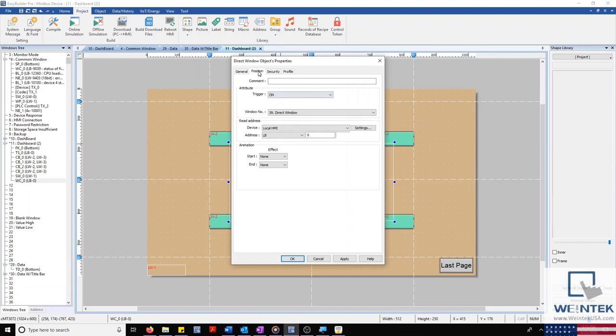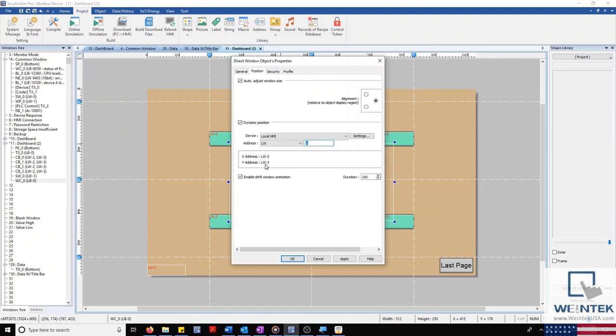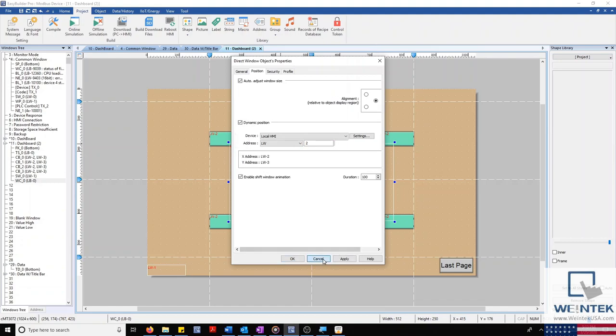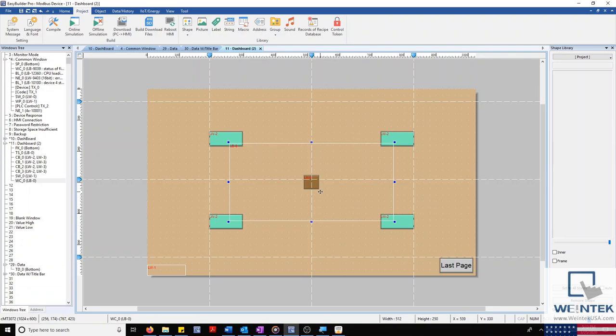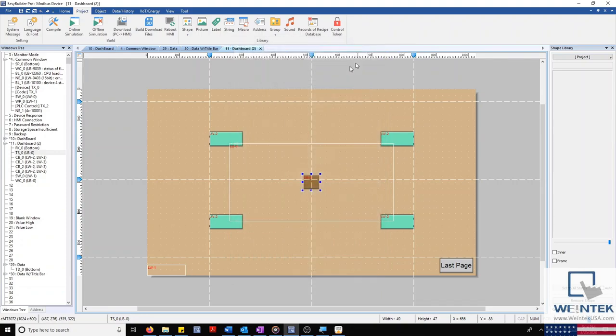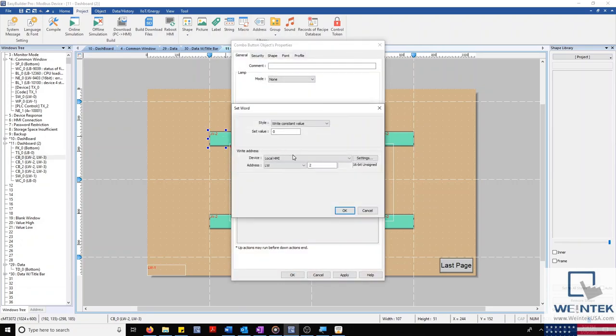Moving over to our Position tab, you'll notice a new feature found with EasyBuilder Pro version 6.04, called Dynamic Position. The Dynamic Position allows our window to change locations on screen to a user-specified location. To demonstrate this, I have a toggle switch located in the center of our screen, as well as four combo buttons located in the four quadrants that our window will move to. Each combo button will write a different value to the X and Y position register of our dynamic direct window.